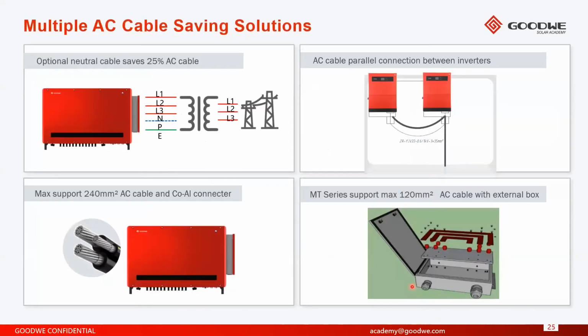We also have savings on the AC cables, so we're able to support larger cables, and also our terminals are compatible with aluminium conductors, which are much cheaper than the standard traditional copper cables that we see in the industry at the moment.